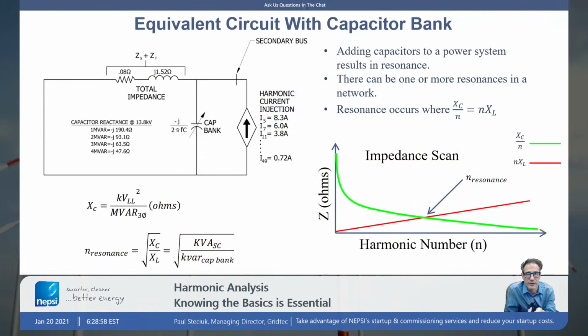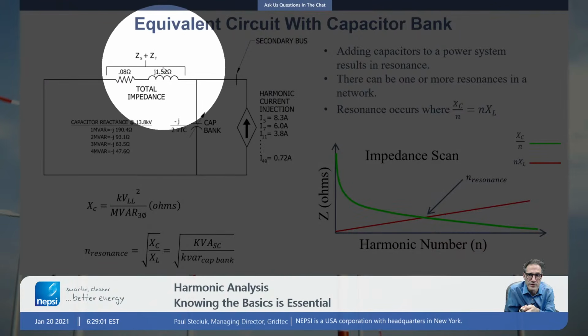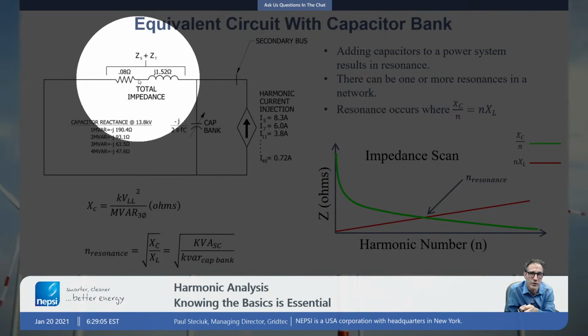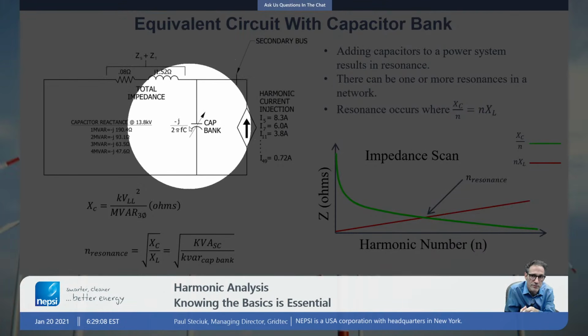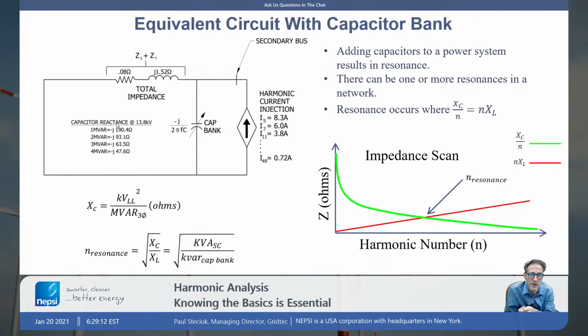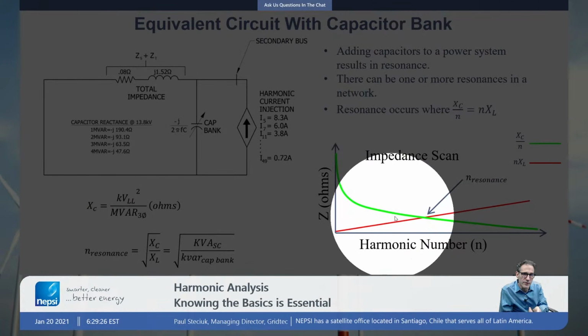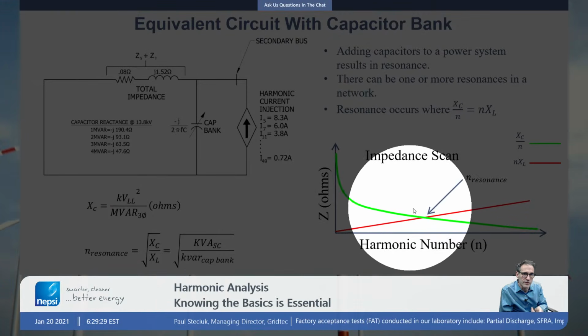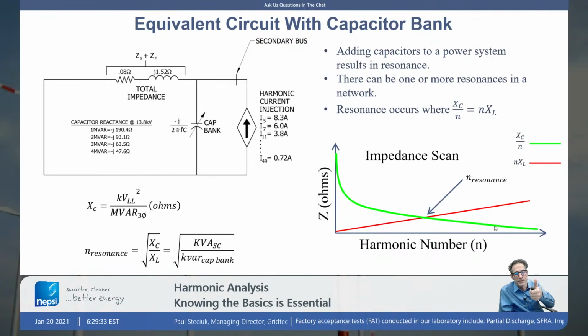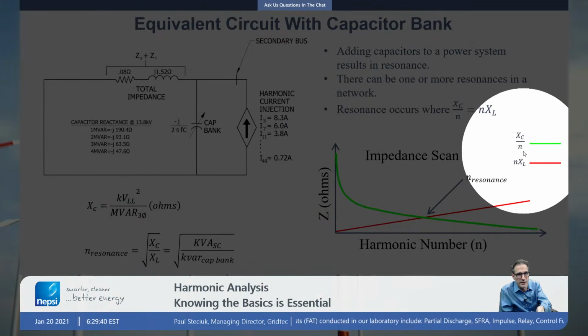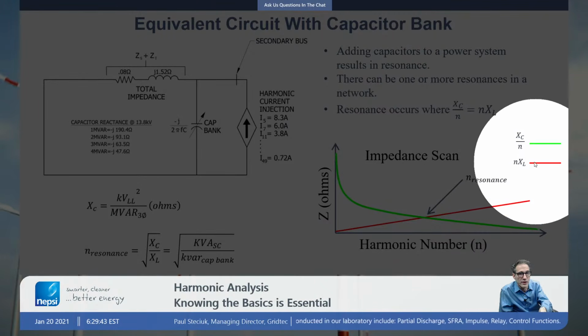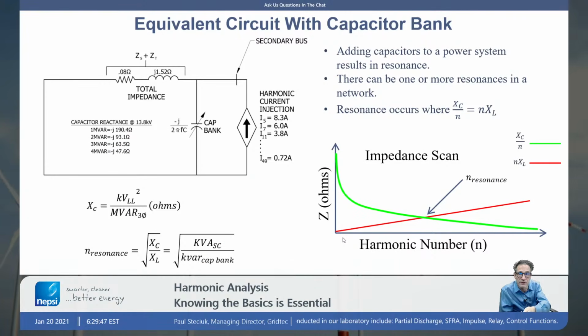We create the equivalent circuit again, and in this case, we got the same value at the source, the 1.52 ohms and the 0.08 ohms. But we have this capacitor here now, which is variable based upon the number of steps online. And it's very common that you have multi-stage capacitor banks that have these variable impedance values. So remember, the green curve here represents the capacitive reactance of the circuit. As we go up in frequency, the impedance is going down because it's X of C divided by n, as we show here. And then we have the red line, which represents the impedance of the transformer up here.